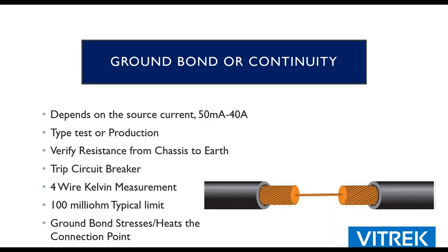On the bottom end, it's always going to be a 4-wire Kelvin measurement. And this graphic here depicts a situation where you could have 100 conductors. If you used a regular DMM with maybe 50 milliamps of source current, you can make this resistance measurement, and it might be within the limit, let's say under 100 milliohms. But if you were to do a ground bond test on it, and if you were trying to pass 30 or 40 amps of current across that single remaining conductor, I know this is kind of exaggerated. Typically, they might only be clipping a few strands when they're stripping the wire, but in this case, we're only left with one.